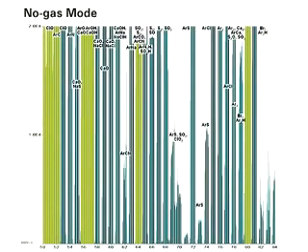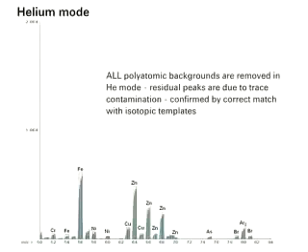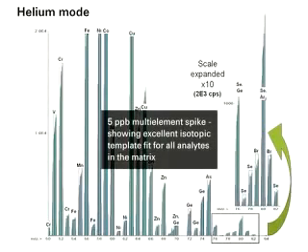This spectrum was acquired in normal mode — that is, with no gas added to the cell. Almost every analyte in this mass range suffers severe polyatomic overlaps, making quantification impossible at trace levels. Now watch what happens when helium is added to the cell: all matrix-based interferences are removed. The remaining elemental peaks are due to parts per billion level contamination in the matrix, confirmed by the correct isotopic template fit. Helium mode has removed all polyatomic interferences simultaneously. Adding a 5 parts per billion multi-element spike confirms all analytes are easily measured in this very complex sample matrix.